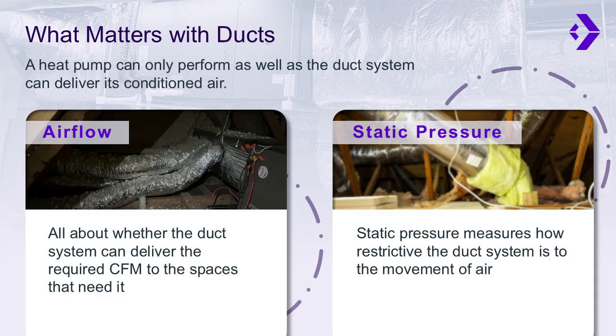First, let's talk about airflow. Airflow is all about whether the duct system can deliver the required cubic feet per minute, or CFM, to the spaces that need it. If the ducts are too small, they restrict airflow, making it difficult for the system to push air to the rooms that need it. On the other hand, oversized ducts can cause balancing issues, leading to uneven air distribution. Both scenarios result in comfort issues, with rooms running too hot or too cold, and the system struggling to keep up.